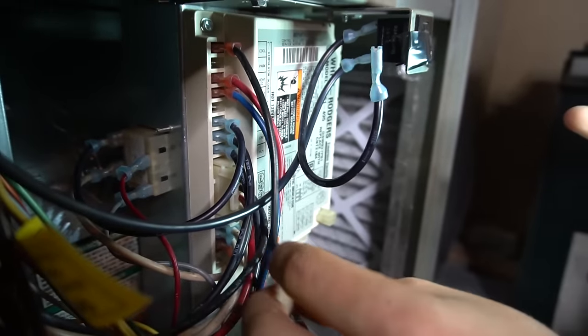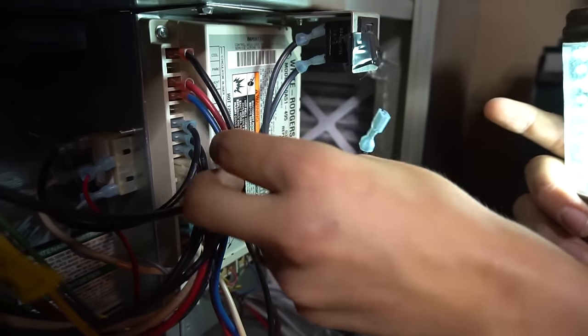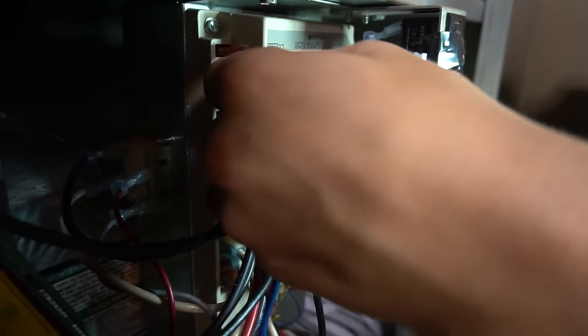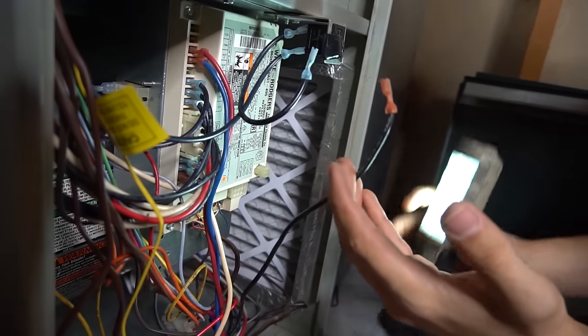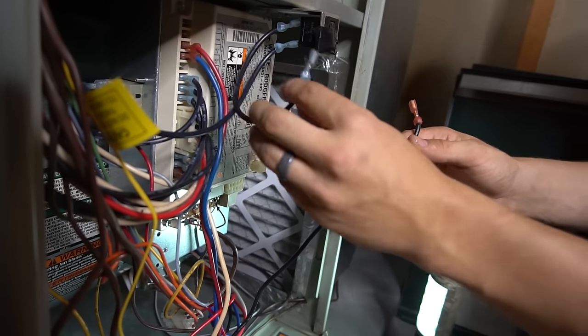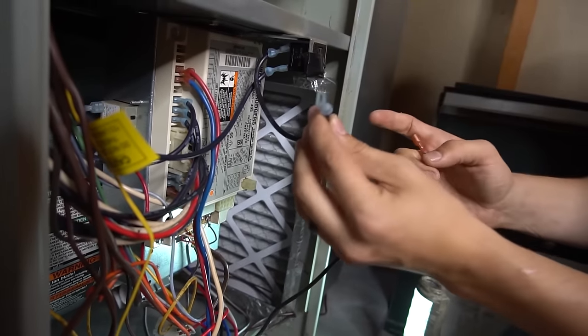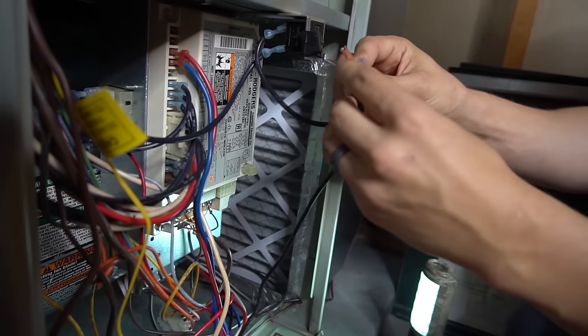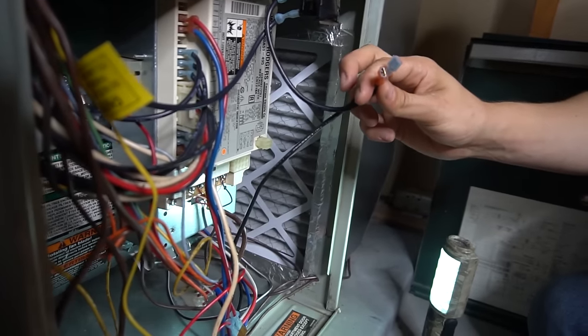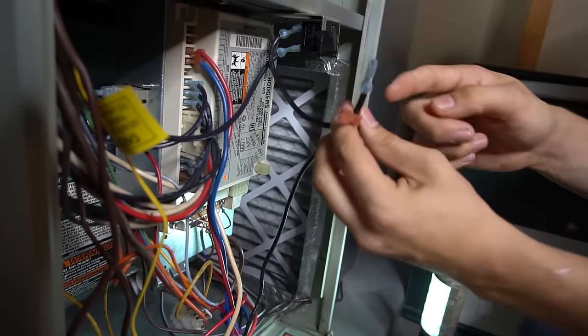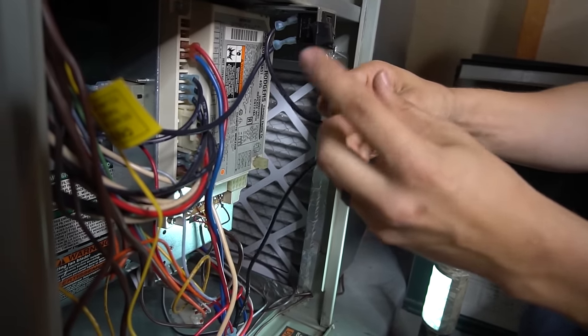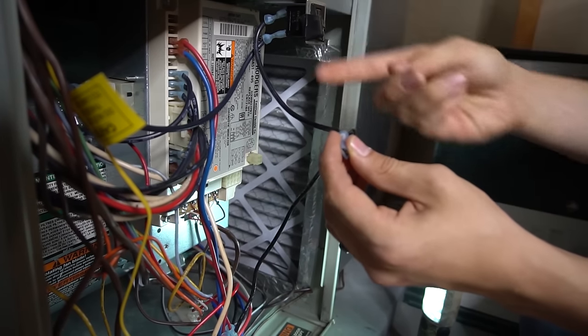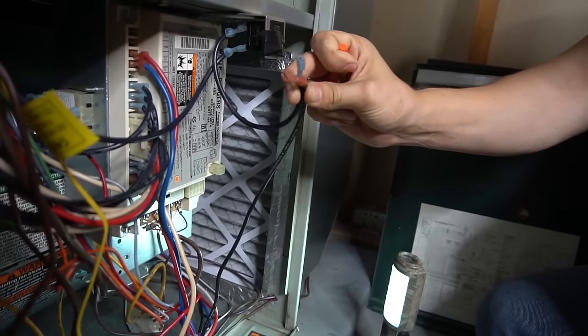And then if you're in the furnace season, you want to pull off your heat wire. If you're in the AC season, which we are right now, you want to pull off your cooling wire, which is this one. Basically, all you're going to do is bypass the control board and send power to the blower motor directly. So this is line voltage coming in from the junction box or the power switch. All you got to do is wire nut. If you want, you can snip these two wires off and then wire nut them together. That'll be sending power directly to the blower motor. So you would snip them both, put the wire nut on, well, strip them, and then put the wire nut on to tie it straight into power.